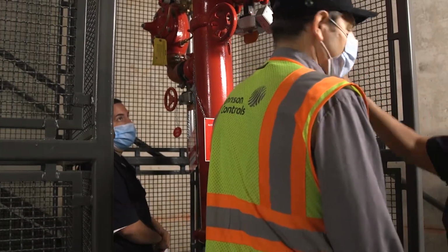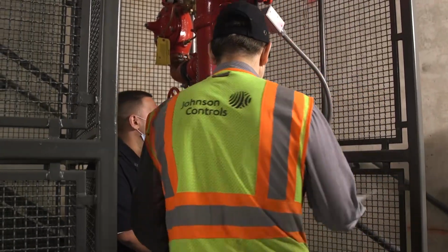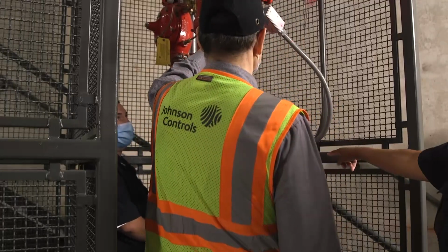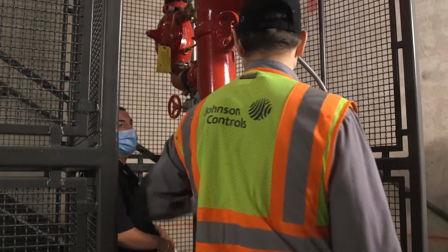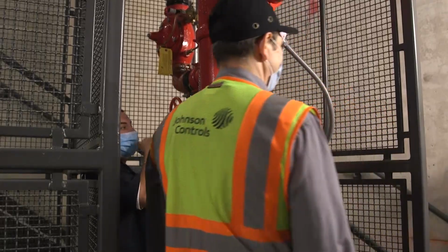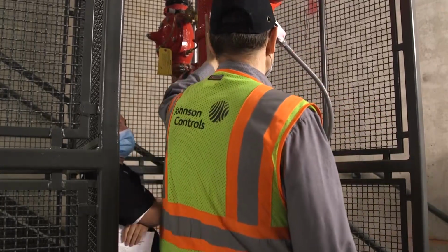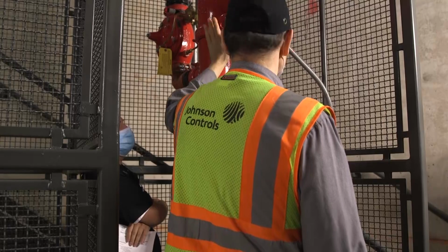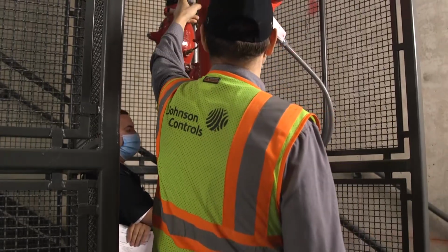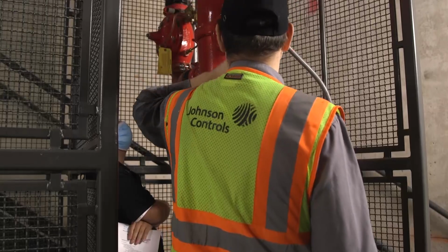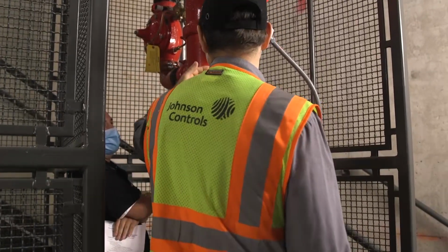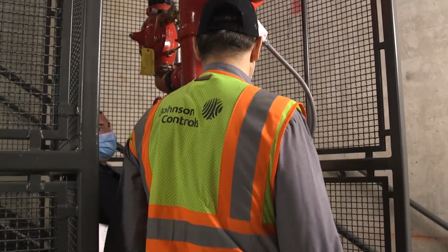So same thing with this one, that one will light up too? This one is the same, but I don't want to touch this because this is a standpipe, right? I don't want to release the water. And it comes up as a supervisory, right? Also supervisory. Any tamper switch is a supervisory. Only the water flow is an alarm, and that corrosion is supervisory also, because the water flow means water is running inside the pipe.